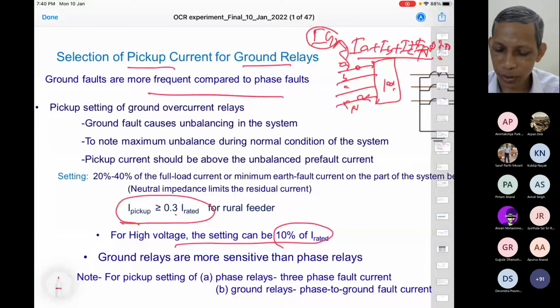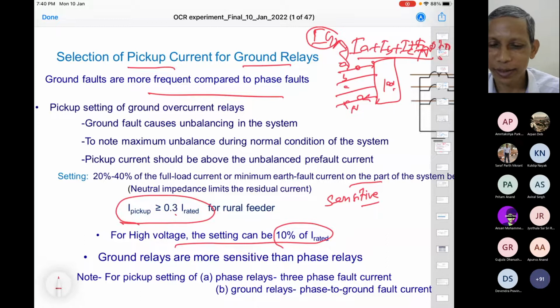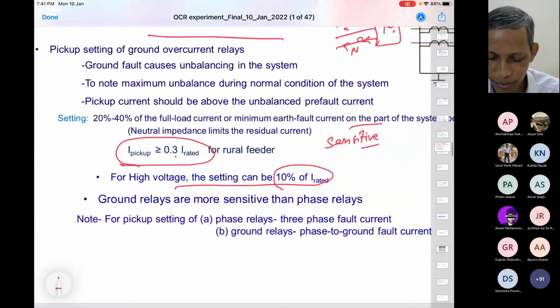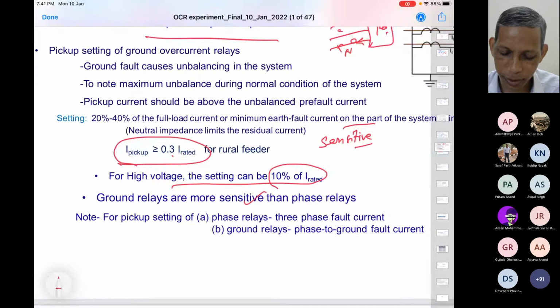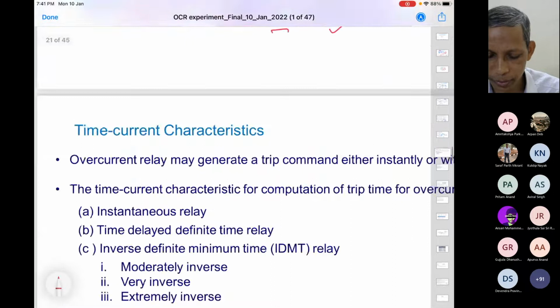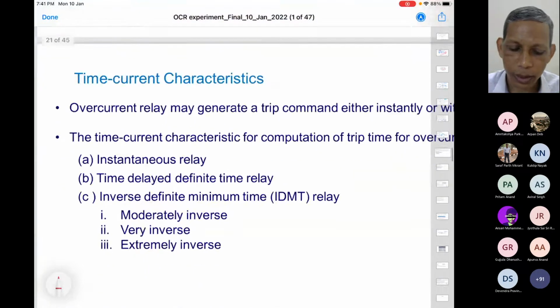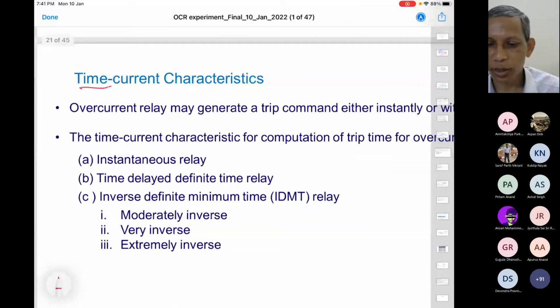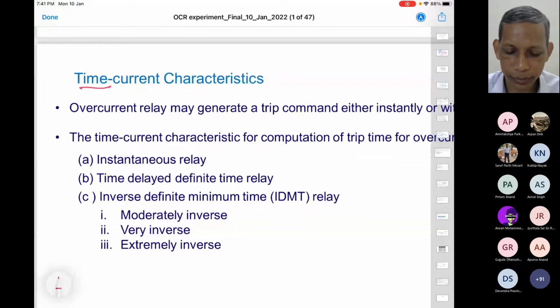So now the question is, which one is more sensitive? I told earlier also, which one is more sensitive? This ground one. Ground relays are more sensitive and more reliable to handle these things. So for pickup setting, consider phase relays: 3 phase faults are taken care of, and ground relays take care of phase to ground faults. Now you come to consider time information in the overcurrent characteristic.